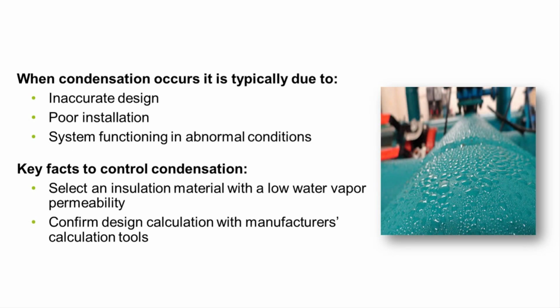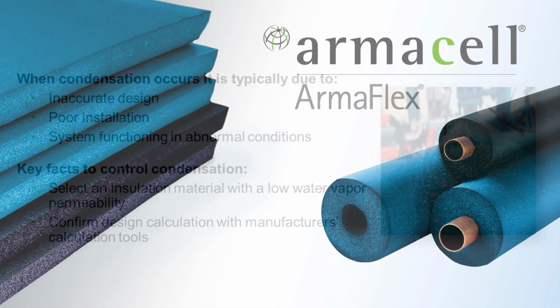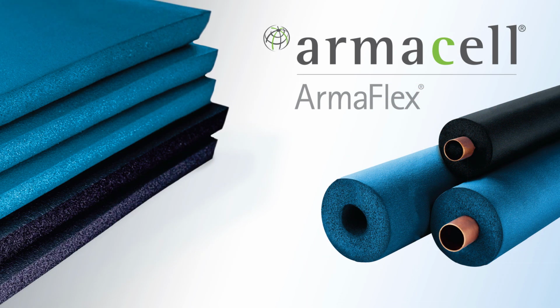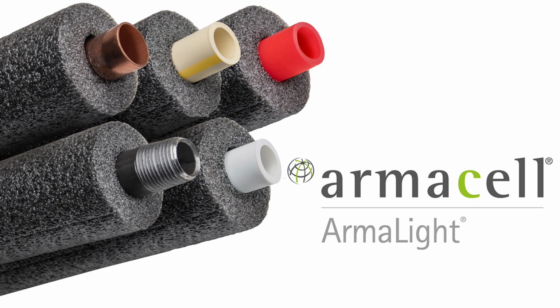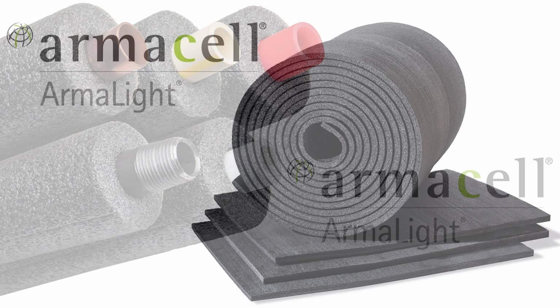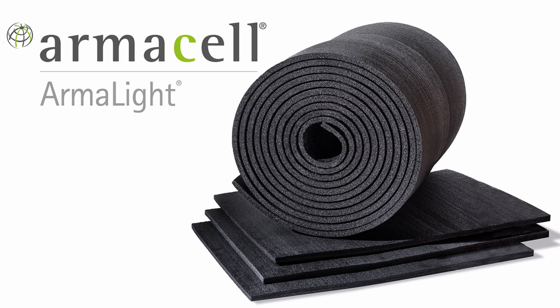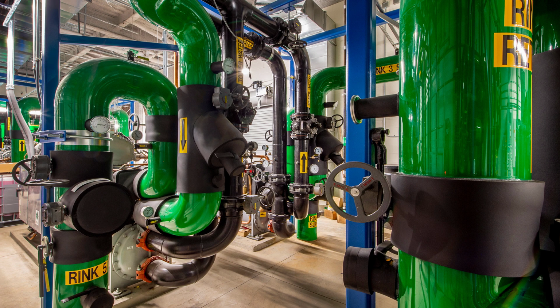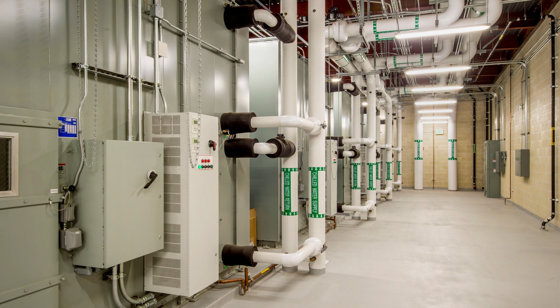This property is critical when considering what material to use to protect from condensation on your below ambient mechanical systems. Systems with lower water vapor permeability will have better resistance to water vapor diffusing to the cold surface and, in turn, condensing. Our ArmaFlex and ArmaLight families of insulation products have low water vapor permeabilities at 0.08 perm-in and below, and are the right choice to protect your below ambient systems.